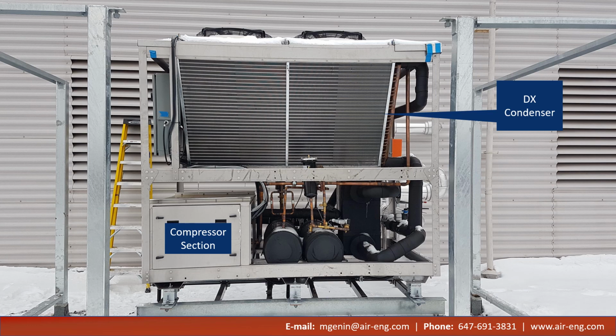The compressors are located inside this sheet metal enclosure. Unfortunately, we can't see them. We can identify the brazed plate evaporator. It is again insulated and it is rectangular in shape, which would indicate it is a brazed plate evaporator.